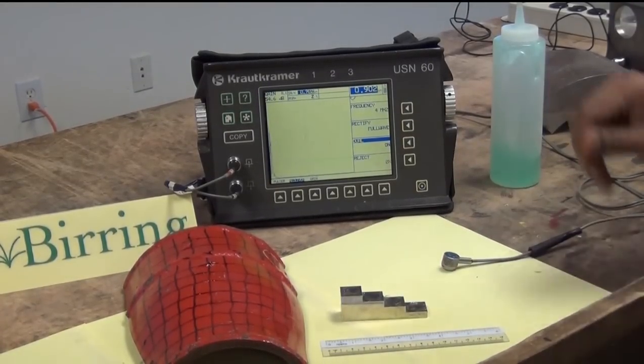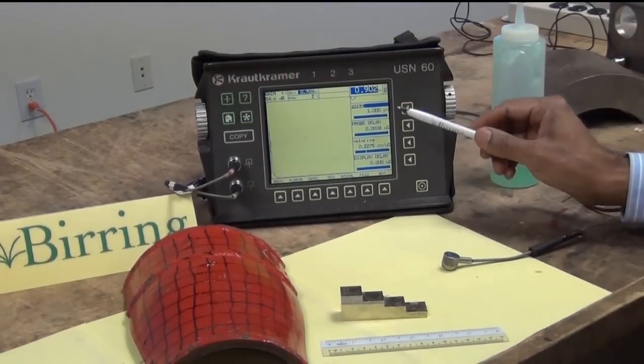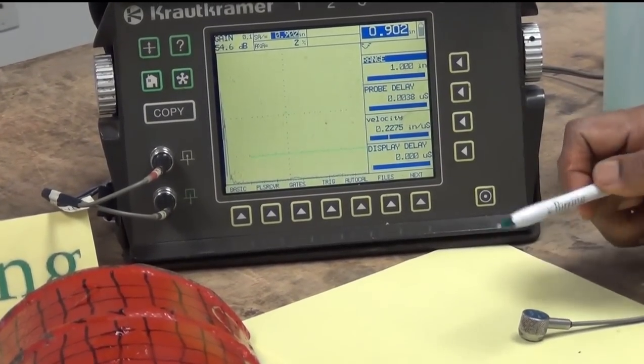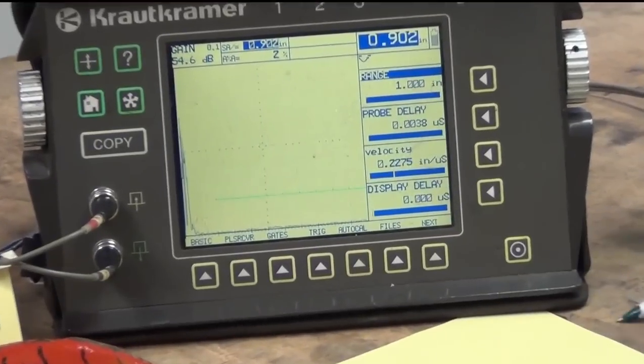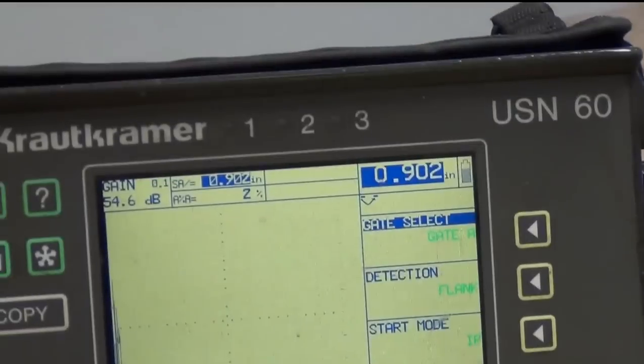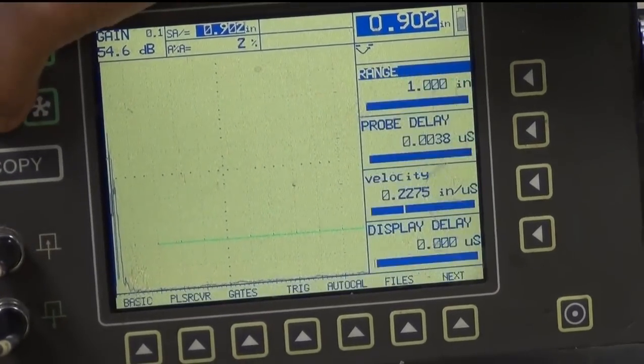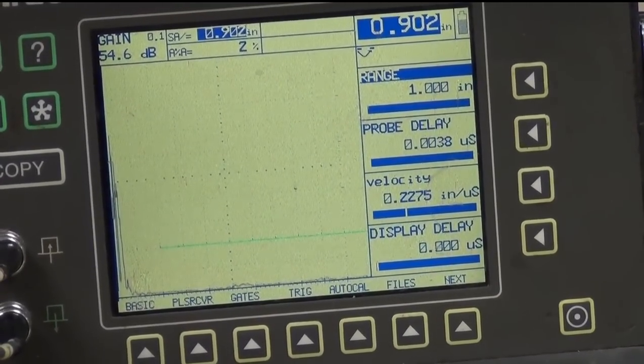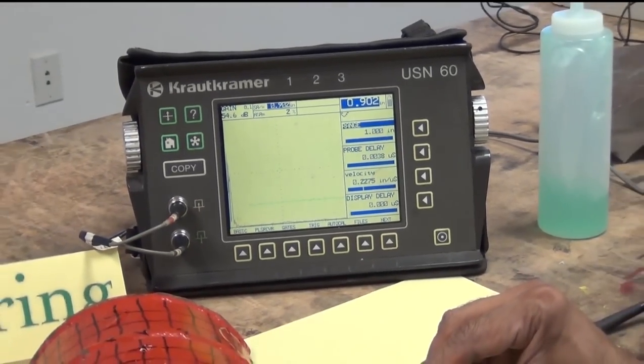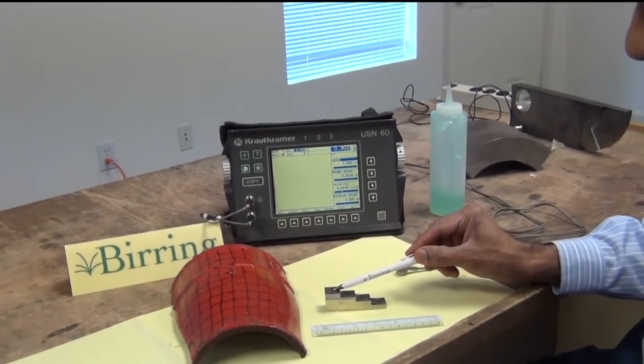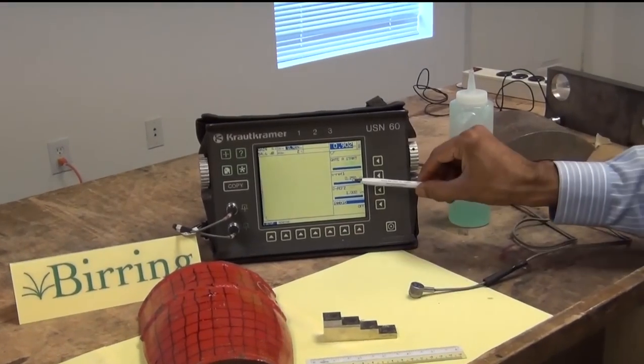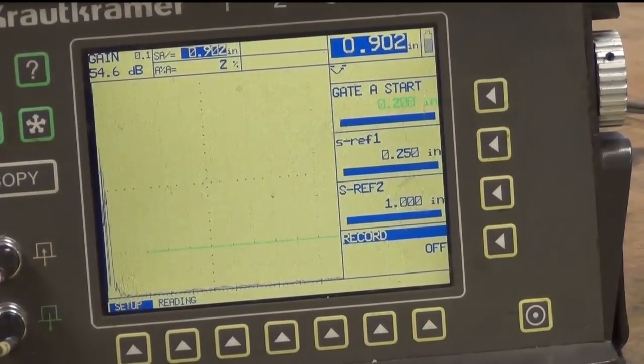Now to start we will set the probe delay to be about zero, velocity approximately 0.22 to 0.23, and I set up the gate to about 20% level. The gate mode should be on the flank, and flank means that it will pick up the first arrival signal. Now in order to do the calibration we will select two thicknesses from the step block, and to cover the range of this pipe I would select 0.25 inch step and one inch step. So in order to do that we go to AutoCal, select 0.25 here and 1.0 inch here, and now I am ready to do the calibration.